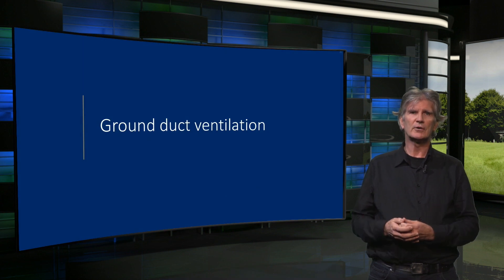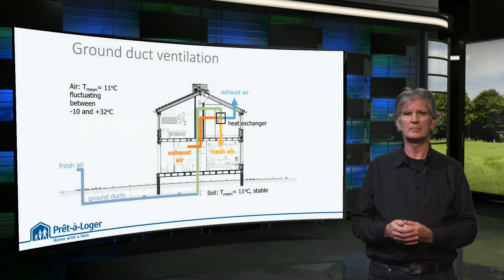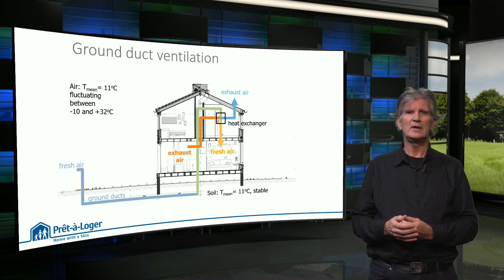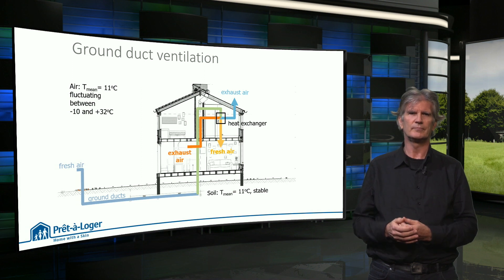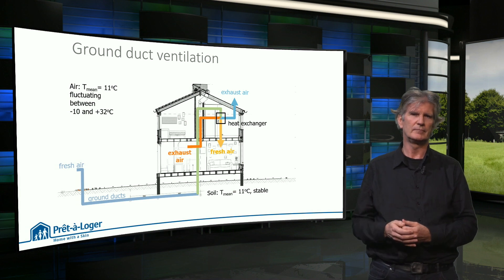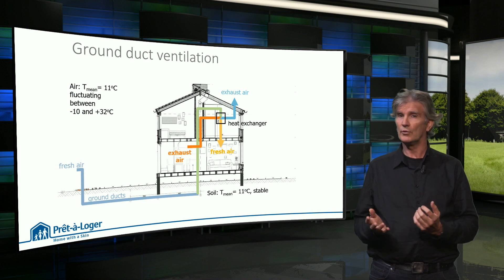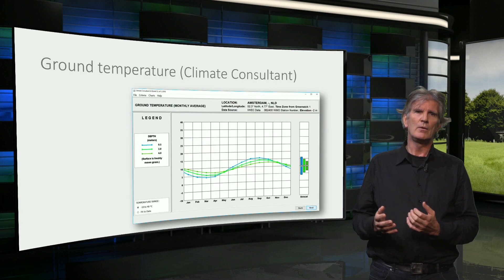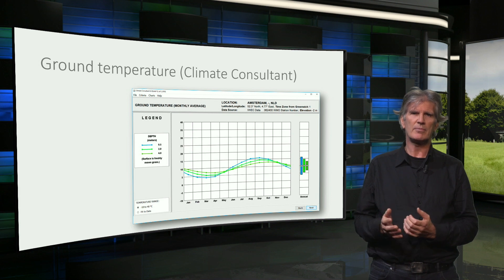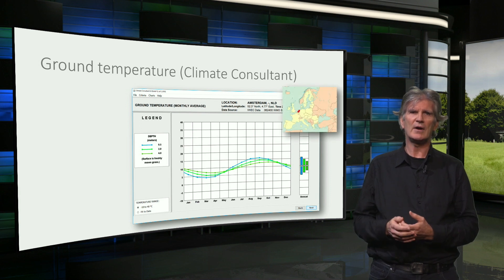Finally, I'll show you a completely different way to exchange heat: ground duct ventilation. Here the incoming air for the ventilation system is let through a duct that is buried underground at a depth of 1 to 2 meters. The ventilation air is preheated or precooled to the ground temperature before it enters the building. Depending on the ground temperature at your location, this can help to reduce the heating demand in winter or the cooling demand in summer. With the program Climate Consultant, you can find the temperature fluctuation in the ground at a depth of 0.5, 2 and 5 meters — here for instance, the graph for the Netherlands.